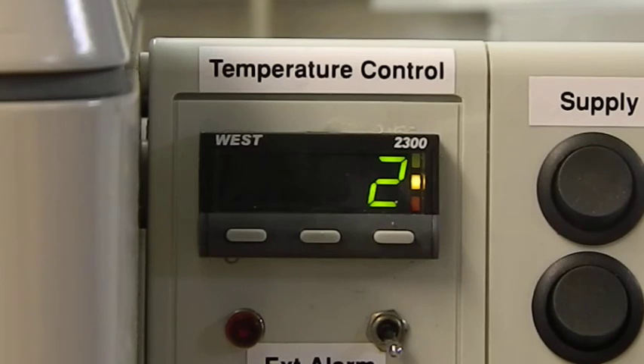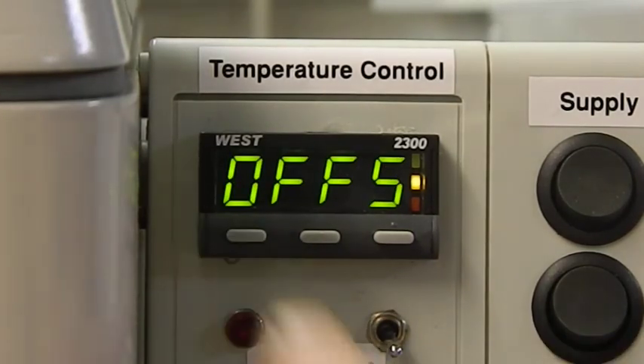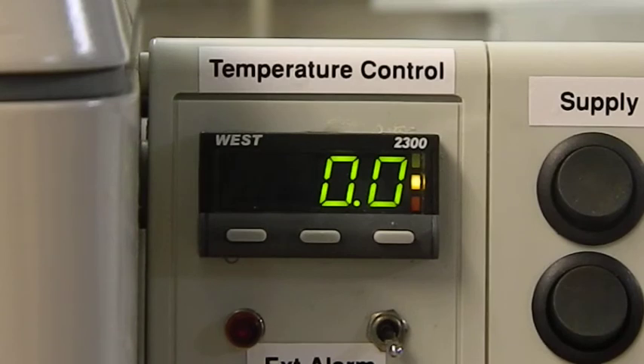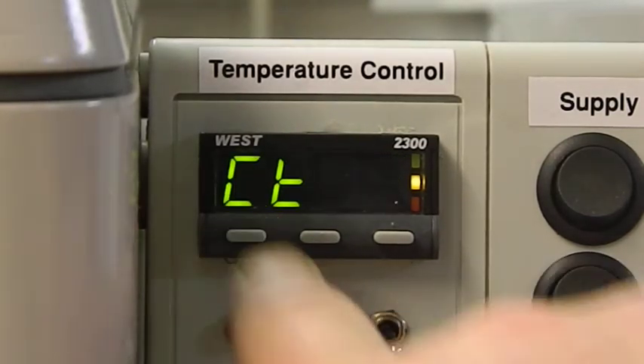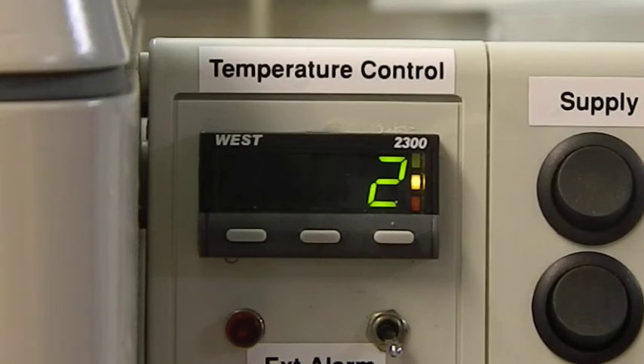Filter. This is a way of damping down the readings that come back from the sensor. If you've got a sensor that's giving you slightly erratic readings, this will take out the error. We'll put in some damping. It'll take out the error factor and allow the unit to control. Offset. This is the calibration parameter for the sensor and the controller. We'll cover that in another video, also on YouTube, which you can access from the website, but we'll pass over that one for now. CT is the cycle time.